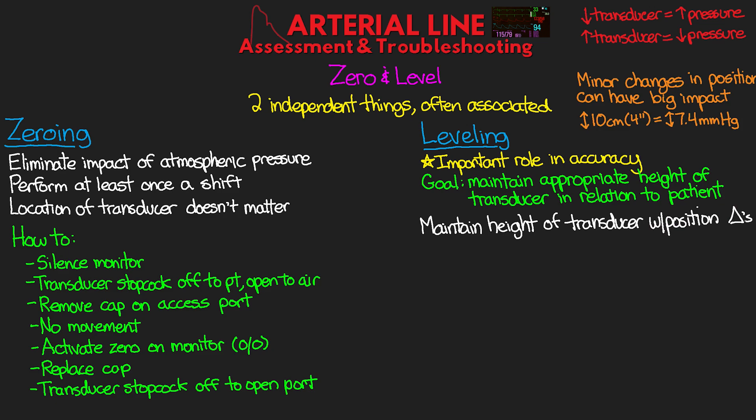If the transducer is below the proper level, we'll see a higher pressure than what it actually is. If it is above the proper level, we'll see a lower pressure. For example, if you've lowered the bed but didn't move the transducer, it's now higher than it was — giving you a falsely low blood pressure reading, which could lead to improper treatment.